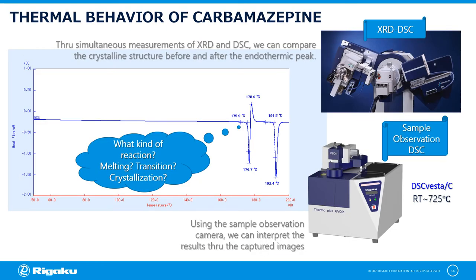One of the common problems in DSC measurement is the interpretation of results when unexpected peaks appear in measuring unknown samples. We can verify this through cycle measurement in DSC, but XRD DSC is the easiest way to understand changes in crystal structure. In XRD DSC, the XRD data is added to the DSC information to determine whether the endothermic peak in the DSC is a crystal transition or melting. Recently, the use of sample observation DSC that records the live image of the sample during measurement is increasingly becoming popular, and it is often used to accurately interpret the results while looking at the image.